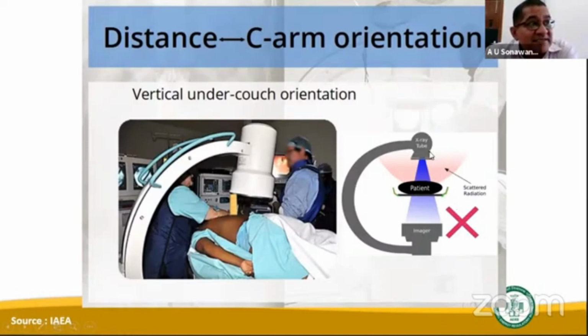We should always avoid having the X-ray tube up and the image intensifier down, because, as I said, 1 milligray in an hour is the leakage radiation level permitted for this tube by the Atomic Energy Regulatory Board. So this scatter may come this side, and here we have the eyes, the thyroid, the radiosensitive organs. Generally, the radiosensitive organs are the breast, thyroid gland, then bone marrow, while bone is radioresistive.